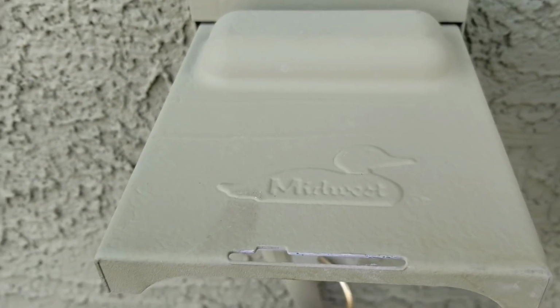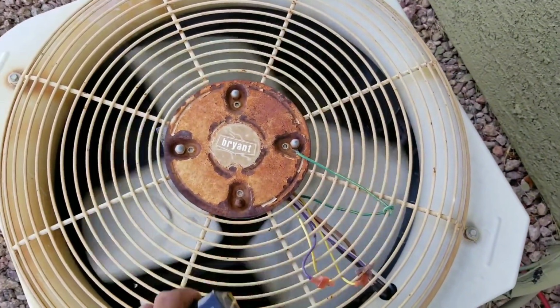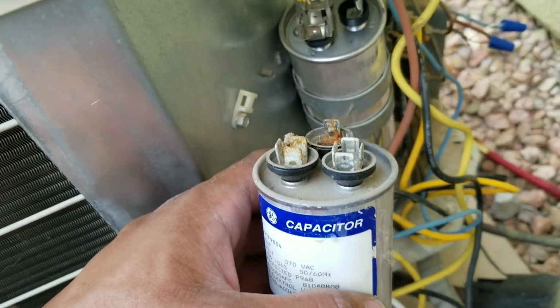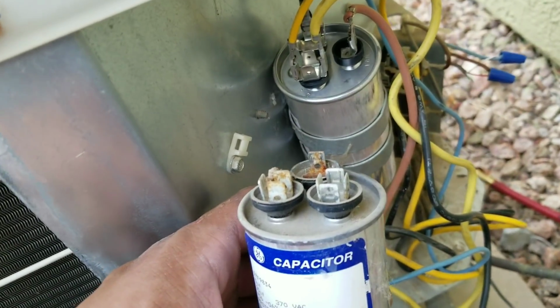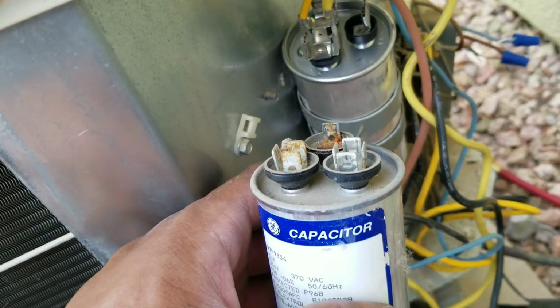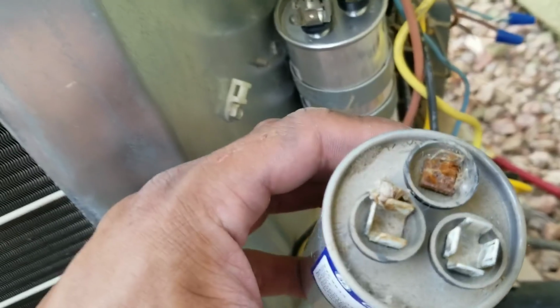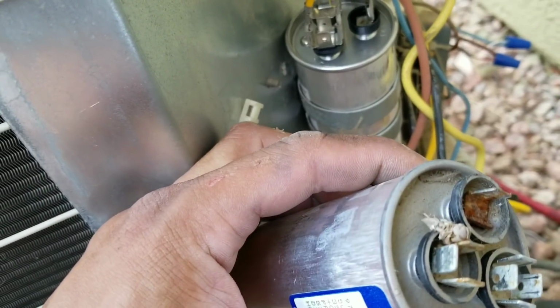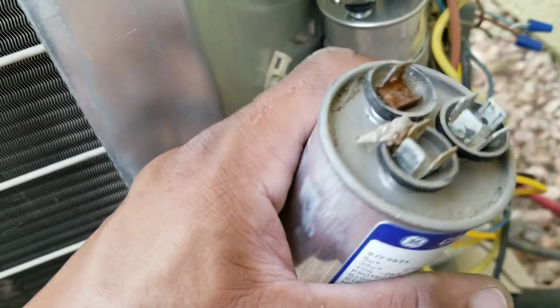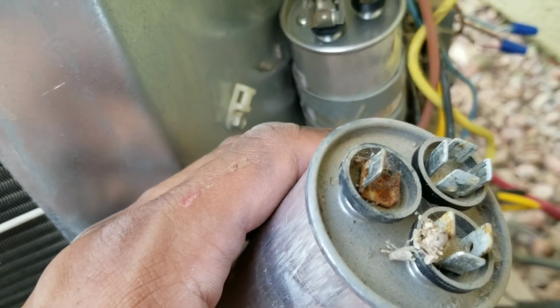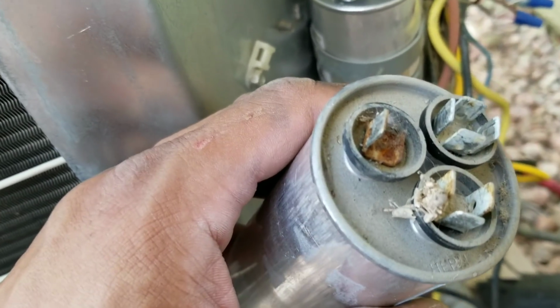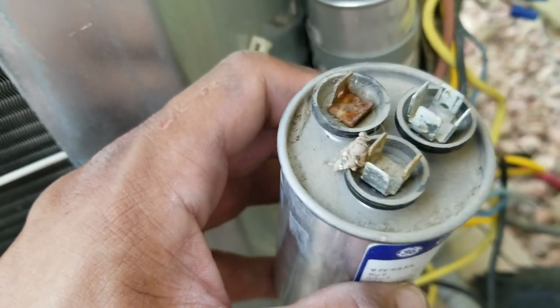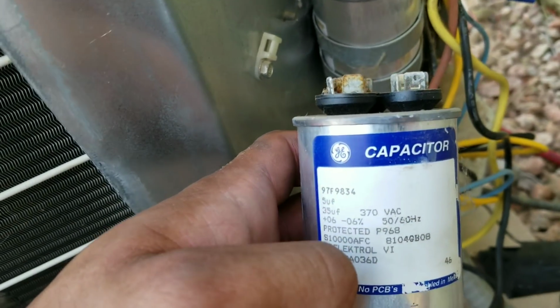This will remove power to my condensing unit. On my channel, I do show you how to remove and replace your capacitor, including the wiring. But here you can see this is the capacitor I removed, and you can see that some sort of bug got into the terminal. This is possibly what caused the capacitor to fail.